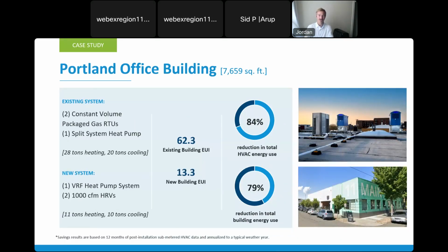Another example, an office building in Portland. I'm intimately familiar with this building. This is the Energy 350 office. As you can imagine, we have many, many sensors and have been studying this for the last 3 years, so we have a lot of data on the system. Before conversion, we had 2 constant volume packaged gas rooftop units and 1 small split system heat pump for a conference room. This was about 28 tons of heating and 20 tons of cooling capacity. We replaced that system with 1,000 CFM heat recovery ventilators and one 10-ton VRF system.